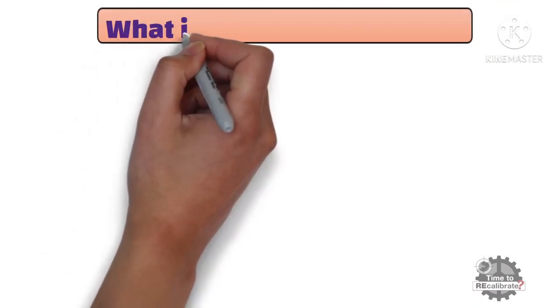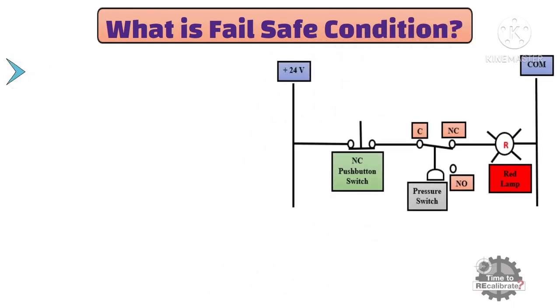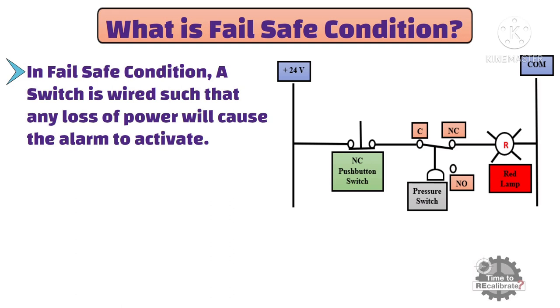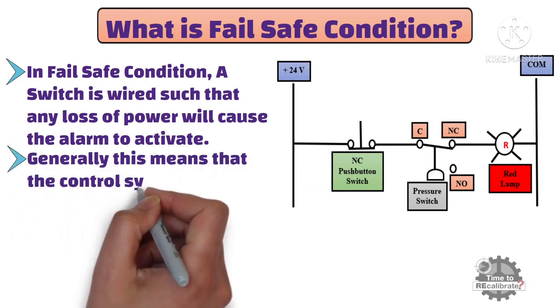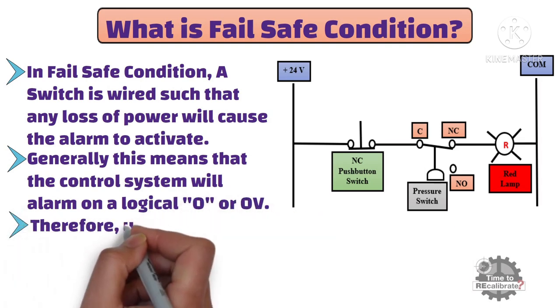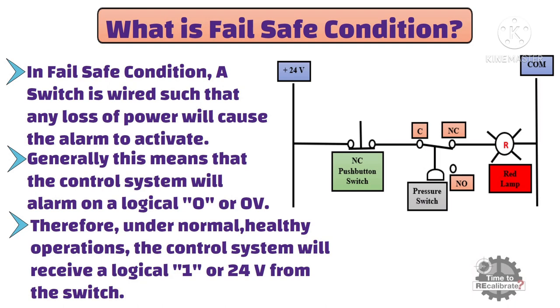Now, what is fail-safe condition? In a fail-safe condition, the pressure switch is wired such that any loss of power will cause the alarm to activate. Generally this means the control system will alarm on a logical 0 or 0 volt. Therefore, under normal healthy operations, the control system will receive a logical 1 or 24 volt from the pressure switch. As you can see from the picture, we use the normally closed contact of the pressure switch, which opens when any power loss or failure occurs. Additionally, a normally closed push button is connected in series with the pressure switch in order to check the system.